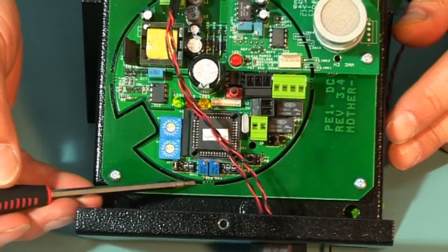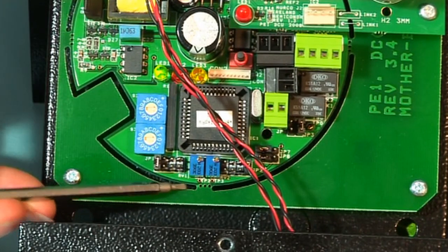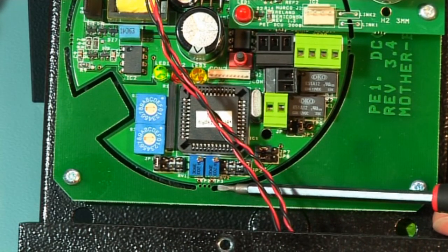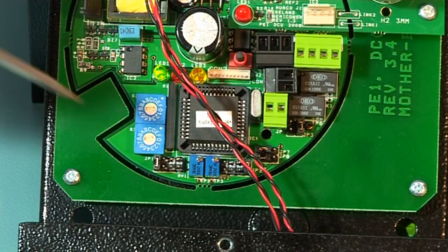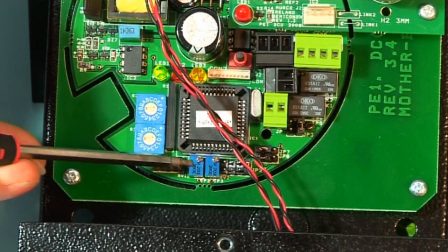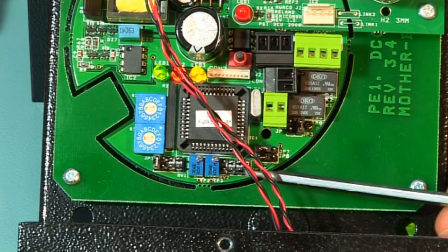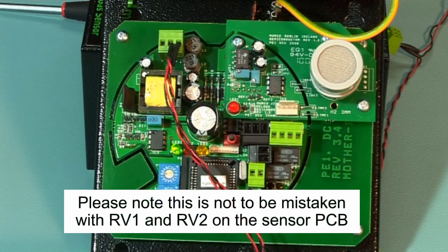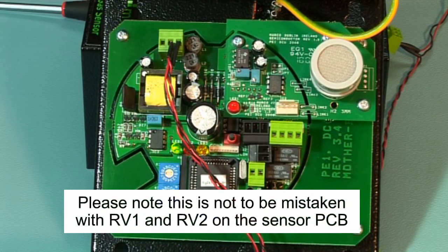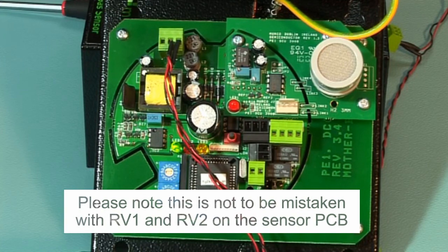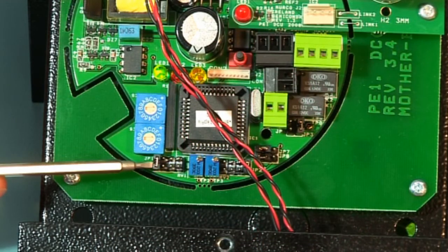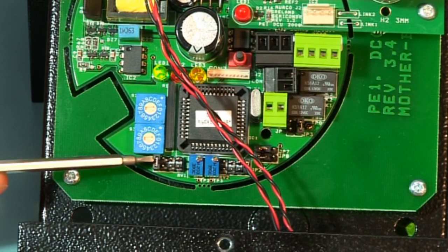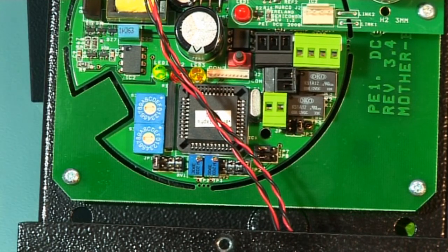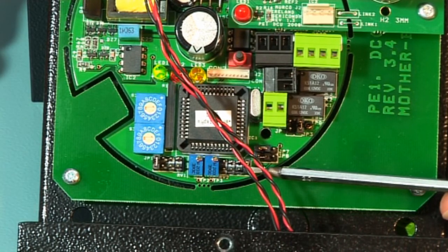The alarm set points are monitored at TP2 for low level and TP3 for high level on the motherboard. The alarm set point adjustment is RV1 for low level and RV2 for high level on the motherboard. Please note that this is not to be mistaken with RV1 and RV2 on the sensor PCB. The delay settings on the units are at JP1 for low level and JP2 for high level as shown here. The jumpers are normally red or black in colour.